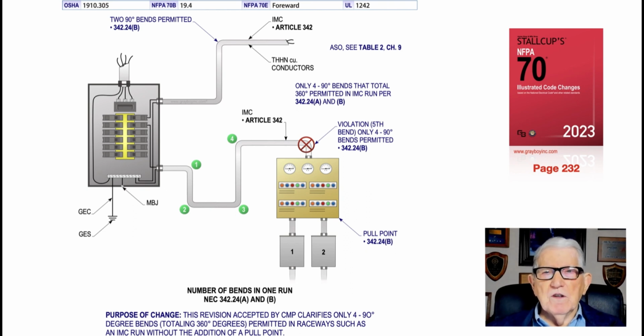Now, looking at the illustration at the very top and the conduit run, you've got 1, 2 90-degree bends. We're fine, see. But now the bottom one shows that you have 4 bends that are okay, but then you put another 90-degree bend, which is a violation of the code. And notice, I could have that other bend, but I'd need to put a pull box between 4 and 5 here, so that I would have a pulling point and it wouldn't be such a strain on the insulation of the conductors when I pull the wire. And that's the whole point of this revision that was accepted by the code panel. So that's what this illustration is illustrating to the users of the code. Don't put more than 4 90-degree bends, including a 45-degree offset, see.